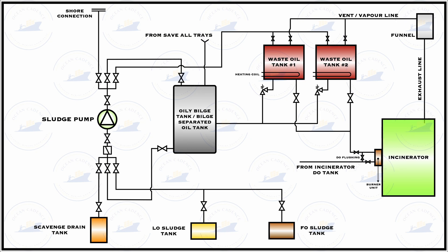The sludge pump is the single entity responsible for carrying out all transfers. While some ships have redundancy for the sludge pump, in most ships it is a single unit. It is therefore very important that spares for the sludge pump fall under the critical spare arrangement of your on-board list. Sludge lines should always be arranged so that there is no vapor locking towards the sludge pump.